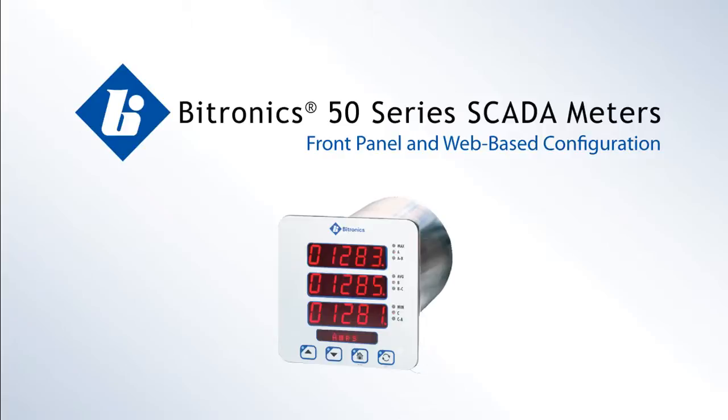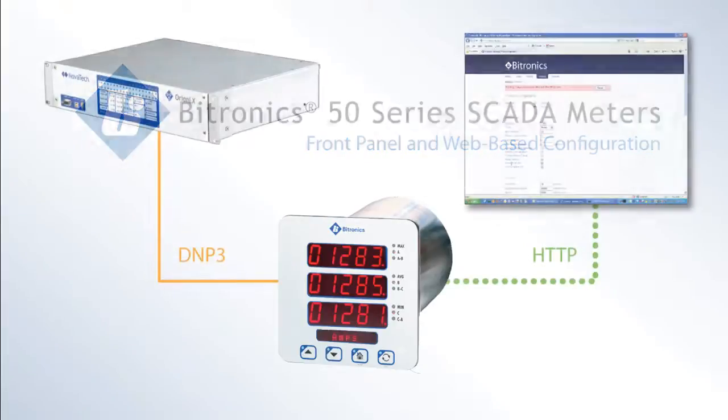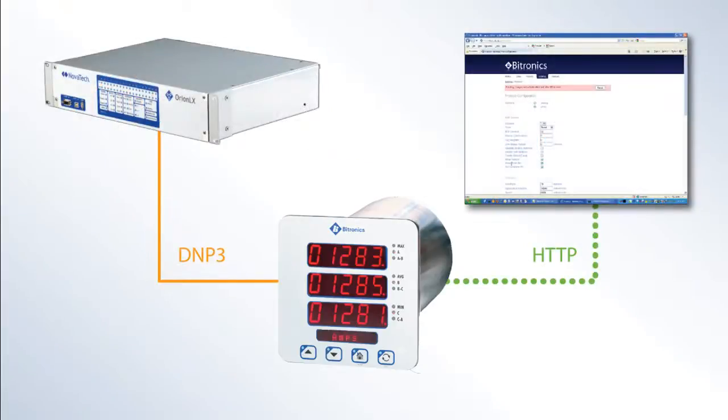This tutorial will describe the procedure for setting up a Bitronics M650 meter to operate in a typical SCADA system. We'll be using DNP protocol and a conventional RS-485 serial connection to an Orion LX which is functioning as the RTU.